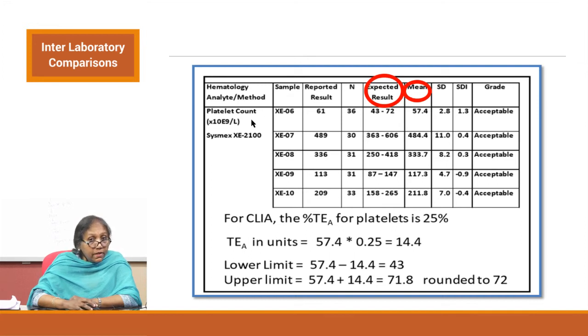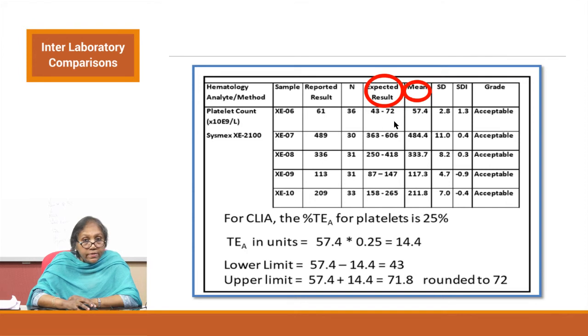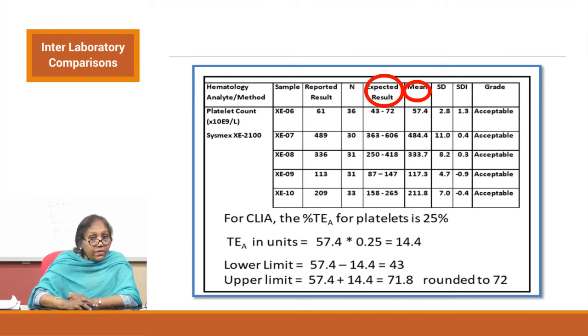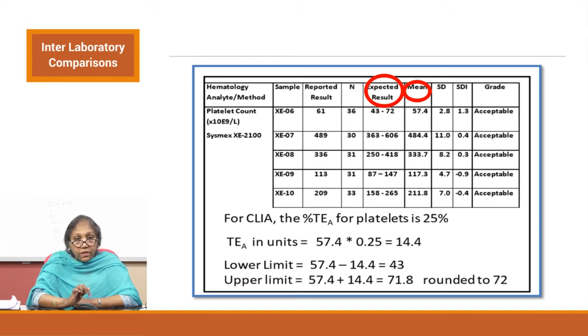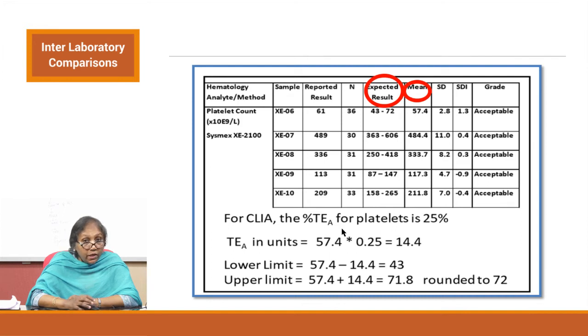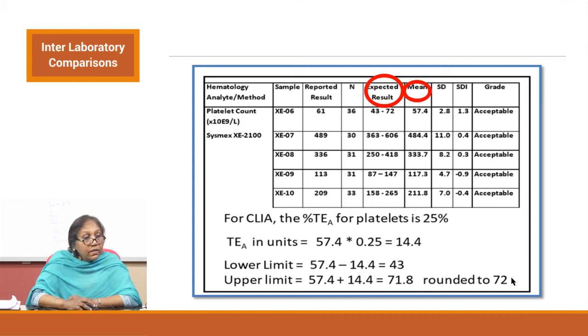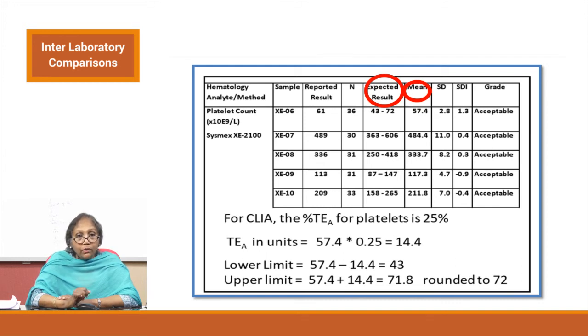For example, in this report the expected result is 43 to 72 when the mean is 57.4. The SD is only 2.8, which does not explain those limits — the EQAS provider is using the CLIA percentage total allowable error for platelets, which is 25%. So 57.4 minus 25% is approximately 43, and plus 25% is 71.8, rounded to 72. The provider is using the total allowable error range of CLIA. It is up to the laboratory to understand how these limits are set.